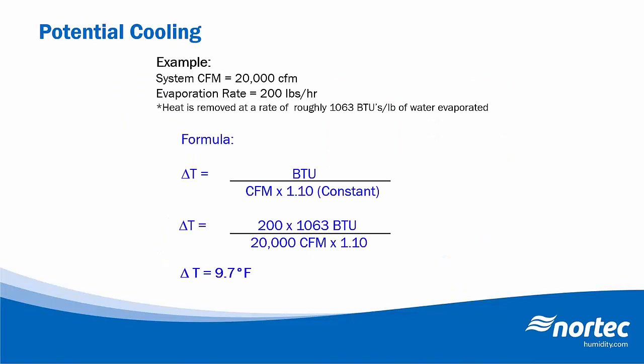So if we look at the same example based on a 200-pound an hour evaporation rate and an air volume of 20,000 CFM, we could potentially achieve a 10-degree cooling effect using an adiabatic system that consumes less than 0.3 kilowatts of electricity. So this is just a rough back of the napkin calculation to give you an idea of what kind of temperature drops we can achieve with this type of system.